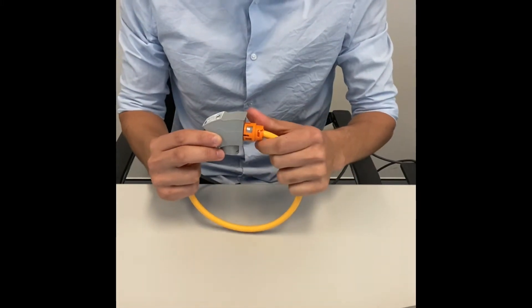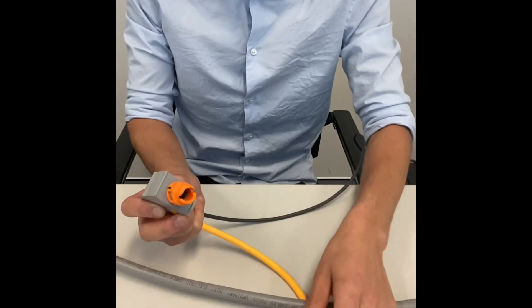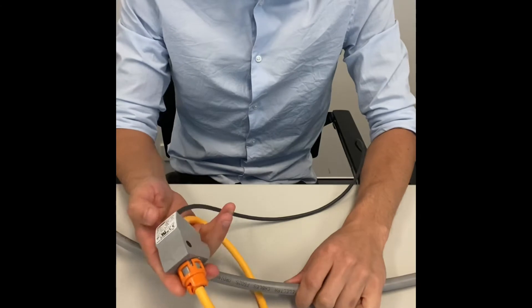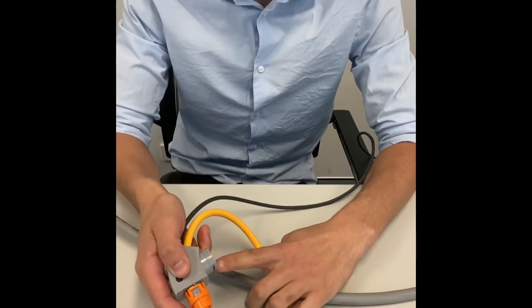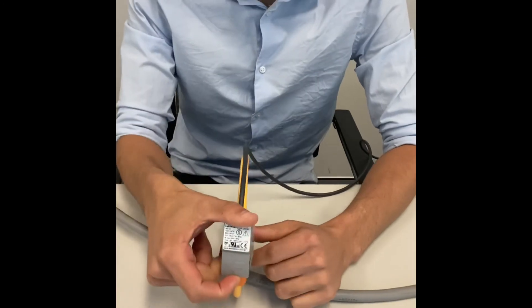With a quick twist of the catch, pull it out, put it through, reattach, and away you go. We also have a mounting point clip available so that you can mount it on bus bars as well. There you have it — a really good solution for retrofitting your CT kits, with no removal of cables or bus bars.